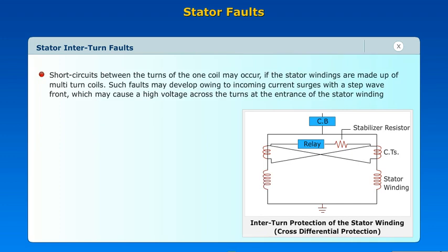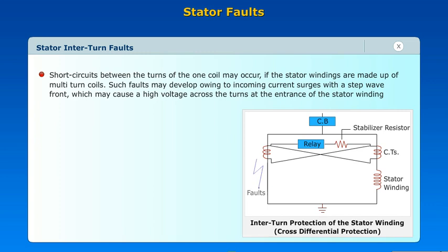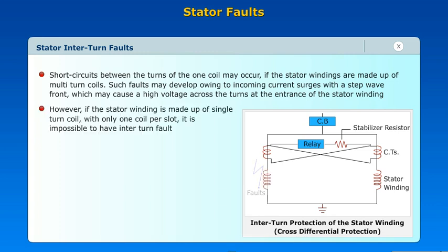Stator inter-turn faults: short circuits between the turns of one coil may occur if the stator windings are made up of multi-turned coils. Such faults may develop owing to incoming current surges with a step wave front, which may cause a high voltage across the turns at the entrance of the stator winding. However, if the stator winding is made up of single-turned coils with only one coil per slot, it is impossible to have an inter-turn fault.